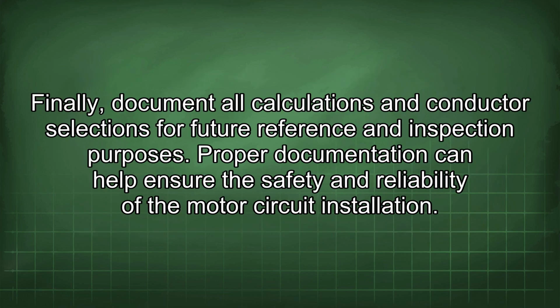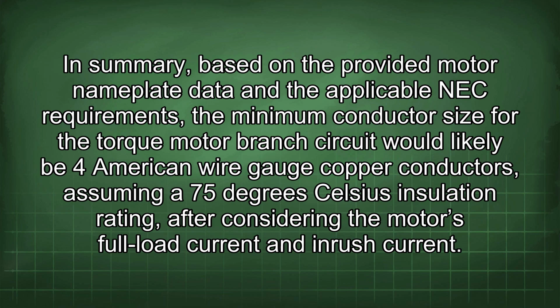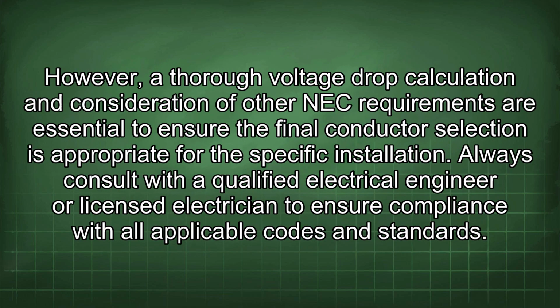Finally, document all calculations and conductor selections for future reference and inspection purposes. Proper documentation can help ensure the safety and reliability of the motor circuit installation. In summary, based on the provided motor nameplate data and the applicable NEC requirements, the minimum conductor size for the torque motor branch circuit would likely be 4 American wire gauge copper conductors, assuming a 75 degrees Celsius insulation rating after considering the motor's full load current and inrush current. However, a thorough voltage drop calculation and consideration of other NEC requirements are essential to ensure the final conductor selection is appropriate for the specific installation. Always consult with a qualified electrical engineer or licensed electrician to ensure compliance with all applicable codes and standards.